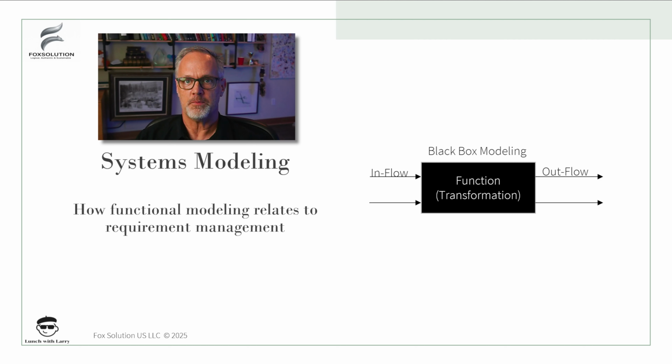So what is systems modeling? Systems modeling is where we create a formal definition between the device functions so that we understand not only how the functions are related to one another, but how they are deployed in each component of the system. And so just at a top level, if you think about it as a black box, we have inflows into the functions. Those inflows are outflows of other functions, just to be clear. Those functions transform the inflows into the outflows. And so if you think about it like that, each requirement characterizes each one of the outflows.